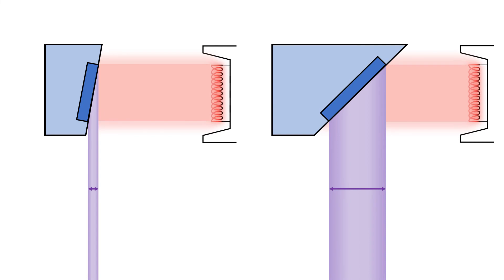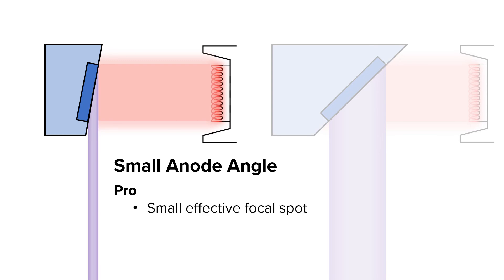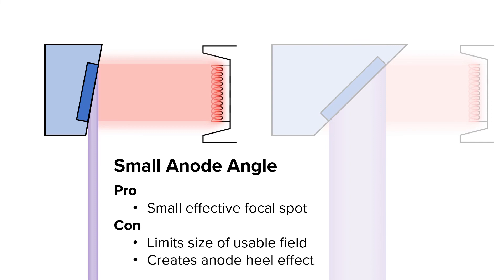There are a number of pros and cons to having a small or large anode angle. The biggest benefit of a small anode angle is it creates a small effective focal spot, thus increasing spatial resolution and recorded detail. A couple cons of a small anode angle are that it limits the size of the usable x-ray field and it creates an anode heel effect.